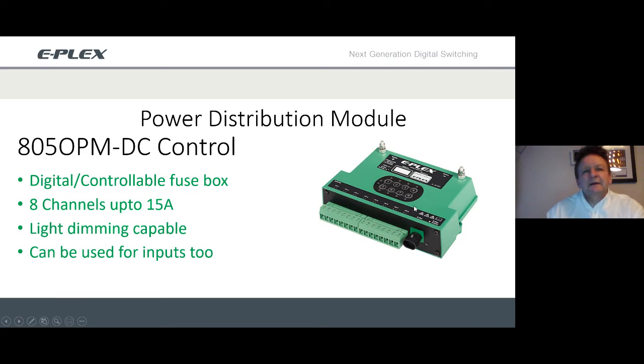So it's basically a controllable digital fuse box. So inside there, in all of those 8 channels, there is a circuit breaker. Now, it's not a conventional circuit breaker, it's a solid state circuit breaker. So that means we can program it to be anywhere between 0 and 15 amps. So one channel can be set to 2 amps, one can be set to 5, one to 3, to 10, to 7, etc. And all of those are controlled by the programming.